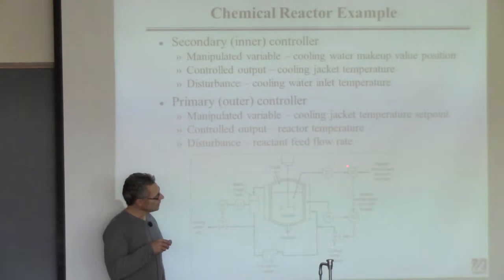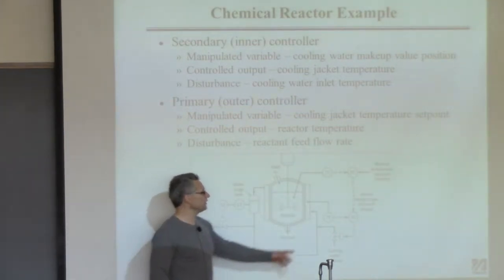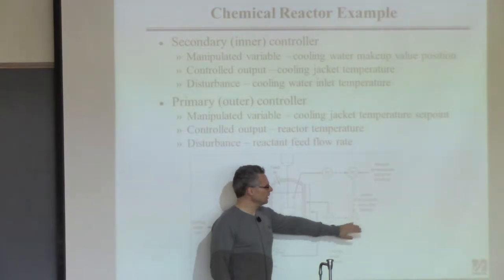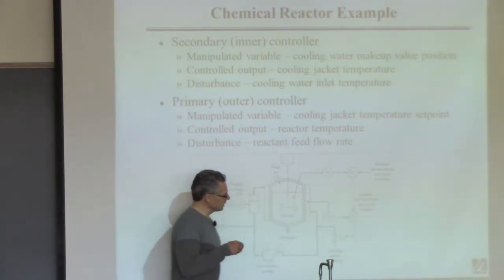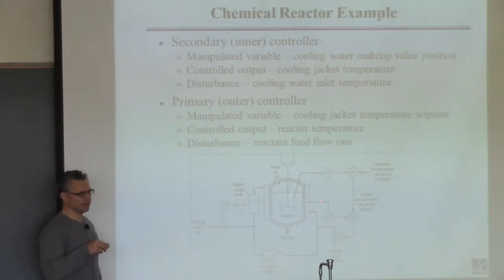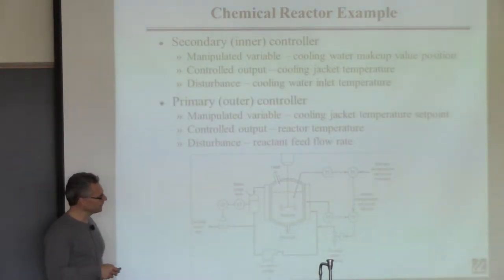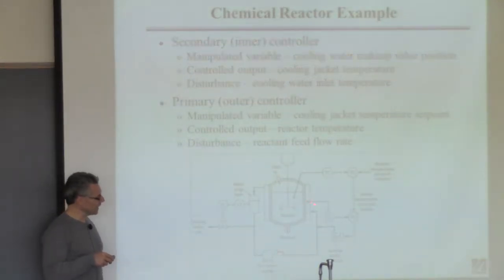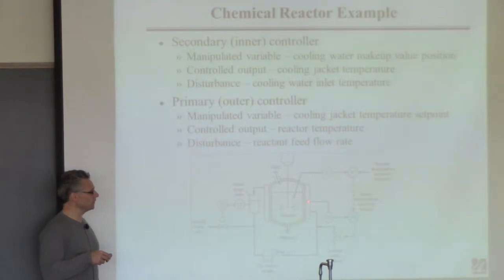And this outer controller just determines what the set point should be for that cooling jacket. What's the advantage of this? Well, if this temperature were to change, you'll see it very quickly in the jacket because the thermal capacitance of the jacket is small compared to the reactor. So the dynamics of the jacket are fast compared to the reactor — you'll see changes in the cooling jacket much more quickly than the reactor.